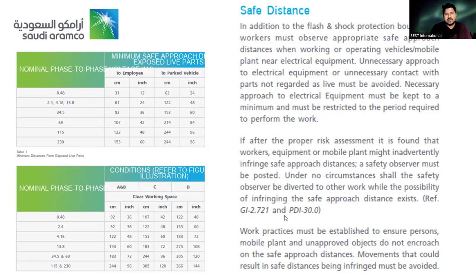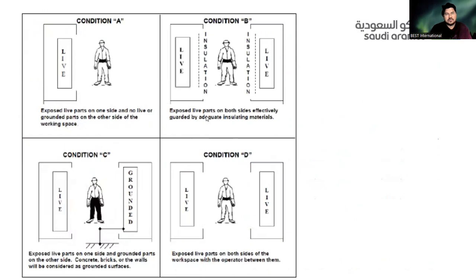As per GI 2.721 and PDI-30.0, this is clearly highlighted, and it should be done after proper risk assessment. It's not like you simply define your own rules, barricade that area, and that's it. You have to follow the Aramco requirements clearly: condition A, how it looks, condition B, then condition C, exposed live parts, and condition D, exposed live parts on both sides. This is also live, but it's condition B, so make sure it's insulated. Then condition C, live and grounded also. Condition D, in both ways we have live, with exposed live parts on both sides of the workplace with the operator between them.